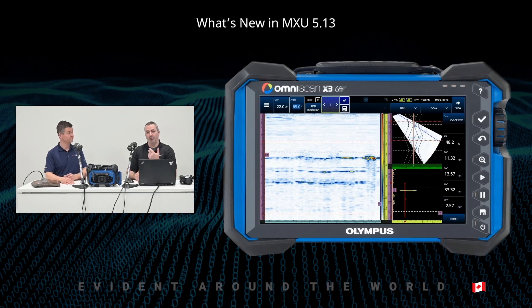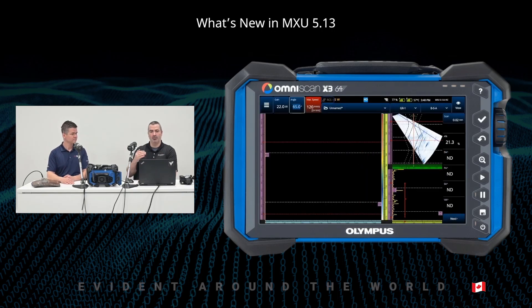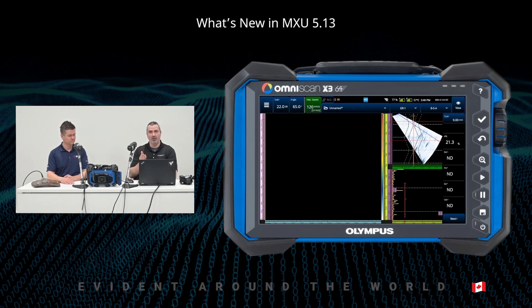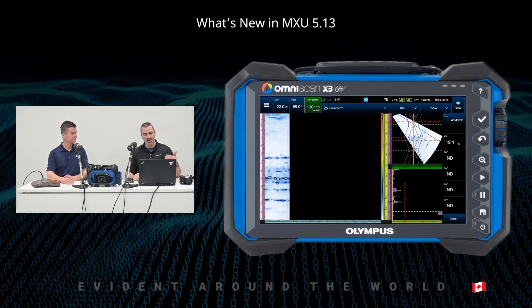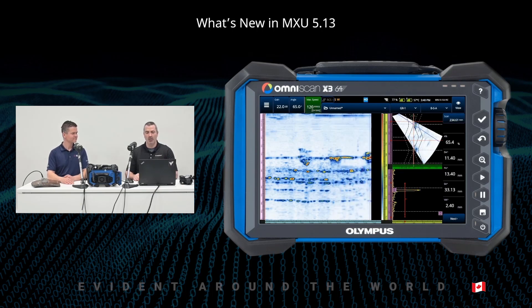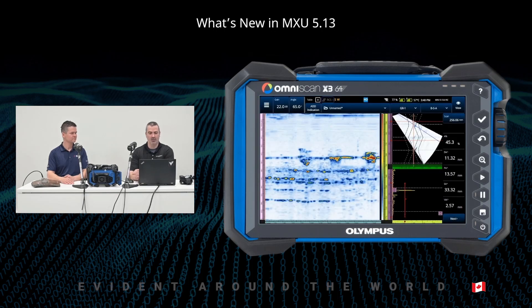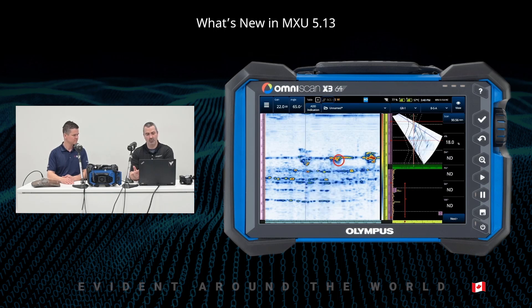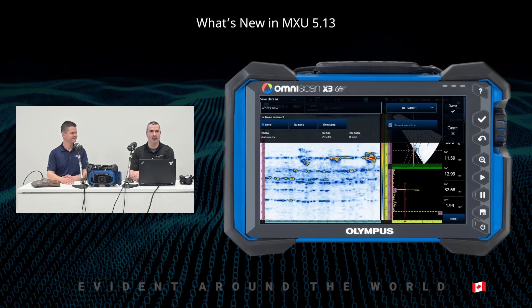The merged B-scan removes the need to scroll up and down. You can activate it directly from the B-scan with a right click or a tap and hold. Now we have the geometry line and indication number one, number two, and number three — very clearly. It's fast screening. You can see where each indication starts and where it ends: indication one, two, and finally indication three, right there at your fingertips.